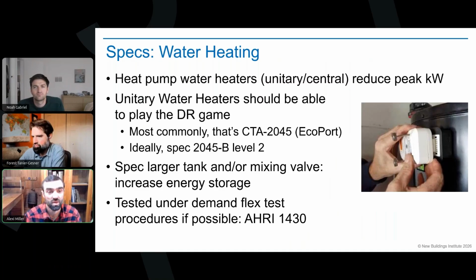If we can, it's great to spec the 2045B Level 2 standard, which makes sure the water heater can do things like advanced load-up, where it takes a signal and preheats the tank a little bit. You can also get there with a larger tank - that's just more thermal energy. A water heater is a thermal battery, period, and a larger tank is a larger thermal battery.